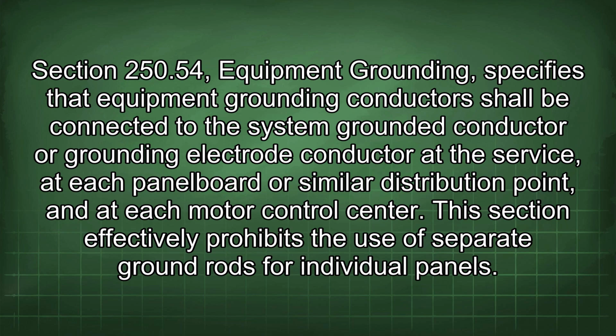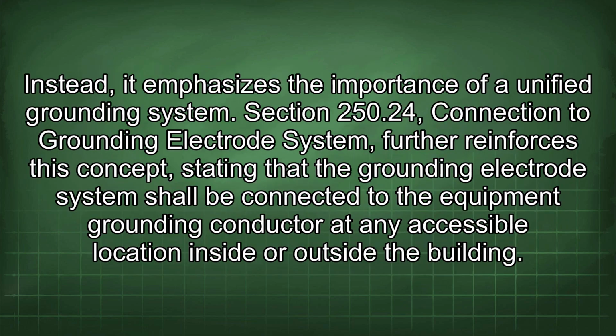Section 250.54, Equipment Grounding, specifies that equipment grounding conductors shall be connected to the system grounded conductor or grounding electrode conductor at the service, at each panel board or similar distribution point, and at each motor control center. This section effectively prohibits the use of separate ground rods for individual panels. Instead, it emphasizes the importance of a unified grounding system.